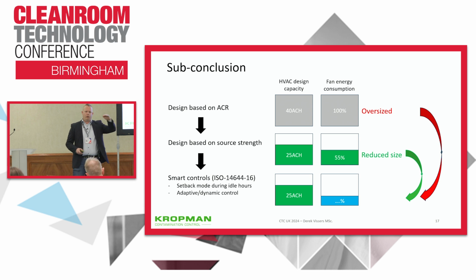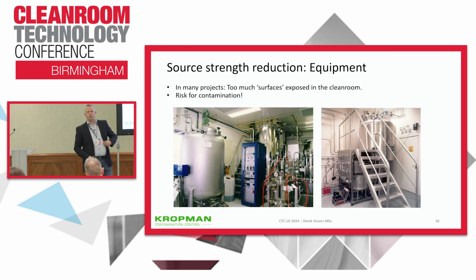And if you have an oversized system, you have oversized components. And if you're going to run at really low air changes due to smart controls, then your components are getting out of the selection range. So it's for that reason, I think it's also better to design based upon source strength instead of any air change rate. But now I'm talking about designing on particle emission in your clean room. But the first thing we should actually do in our designs is trying to minimize the particle emission.